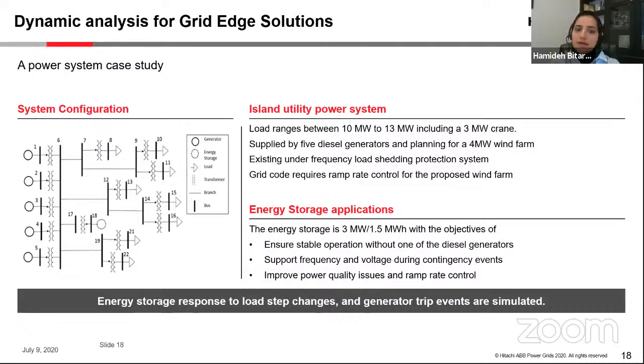As you can see, the island has a peak load of 13 megawatts and has a crane on site, so it's dealing with power quality issues because the crane is a dynamic load that creates frequency fluctuations for the island. The island is supplied by 5 diesel generators and is planning to invest in a 4 megawatt wind farm. It also has some protection system and requires ramp rate control for the future wind investment.